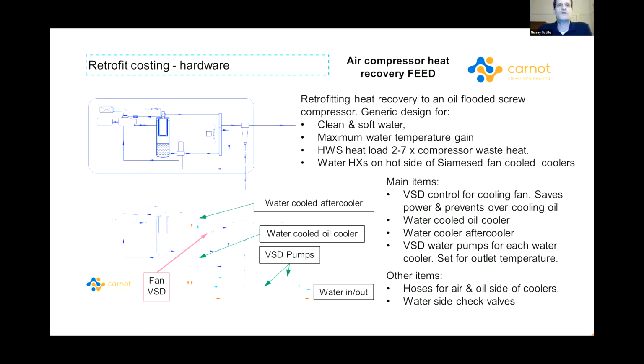There are lots of different ways to do things, and it depends upon what you are planning to do. The intent of this system is to give you the hottest water possible. So small water flows, and it's a generic design for clean and soft water. You'd use this if the hot water system load was, say, 2 to 7 times that of the compressor waste heat, and it also considers the heat exchangers as siamese on the hot water side.